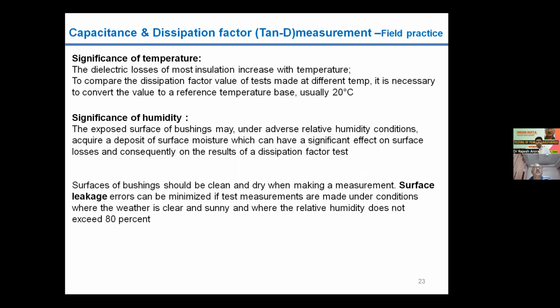What is the significance of the temperature? As I discussed earlier, because of the variation in temperature, the losses inside the insulator may change. Every insulator, when subjected to different temperatures, will have different resistance, and accordingly losses will vary. So it is very important that whenever we do tan delta measurement, as I discussed in the case of resistance, the tan delta value should always be referred back to the same temperature. Means whatever values we have taken earlier, if we measure at a different temperature, they should be converted to the same temperature value. For that, we have an arrangement in the kits also.